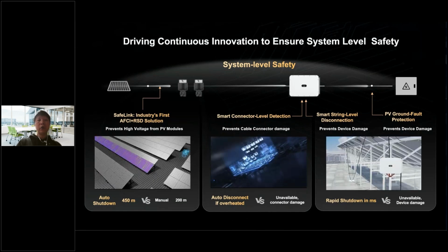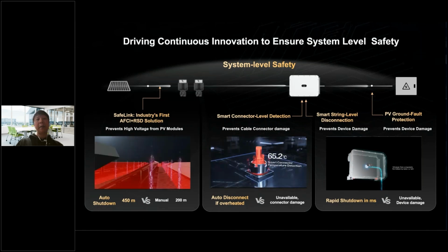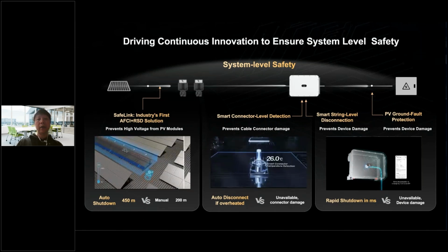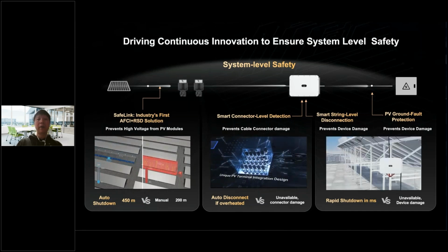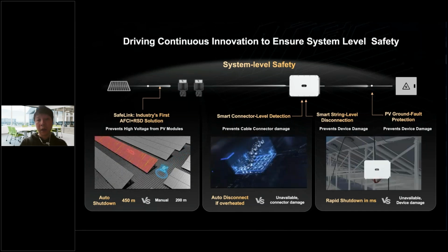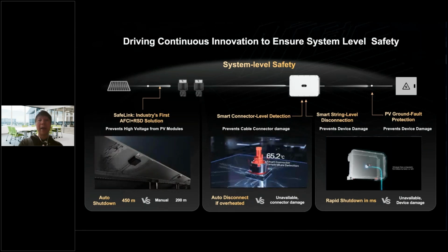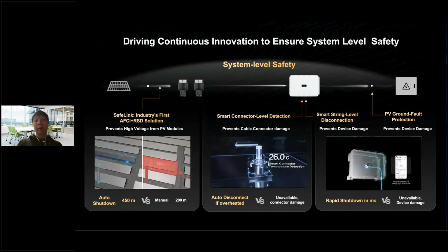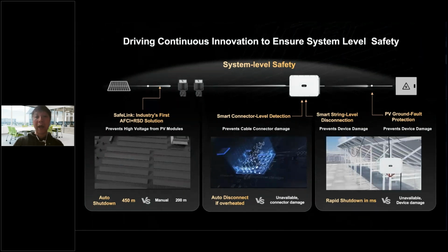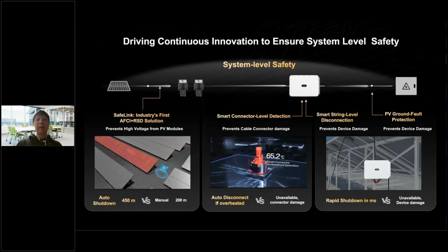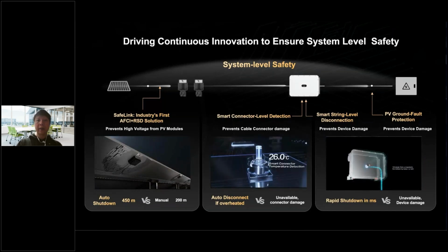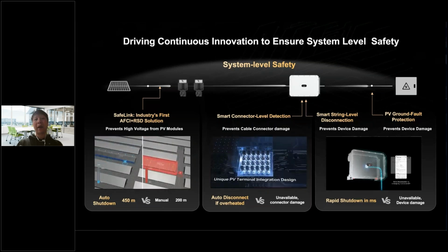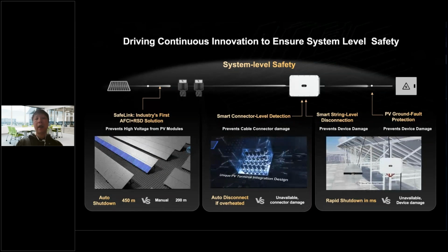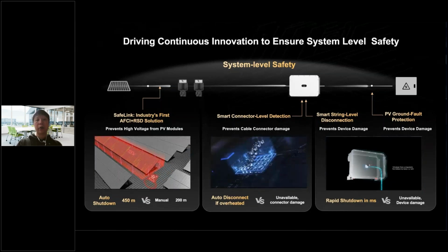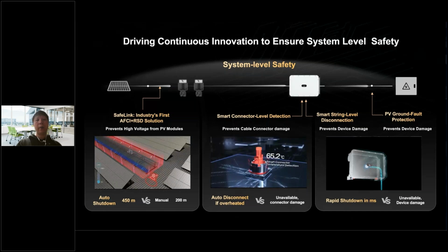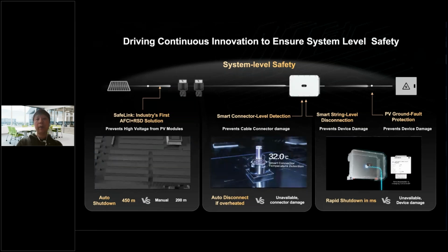Some solutions in the market also have the rapid shutdown function, but when they combine AFCI with RSD, the optimizers cause interference to the arc signals, so the result of the arc detection will be very bad when you add optimizers to your systems. But for Huawei, because we have very precise algorithms, when you add AFCI with RSD together, the optimizers don't affect any signals on the DC side, and our inverters can still very precisely detect the arc from the DC side, and we can shut down if you trigger it 5 times.